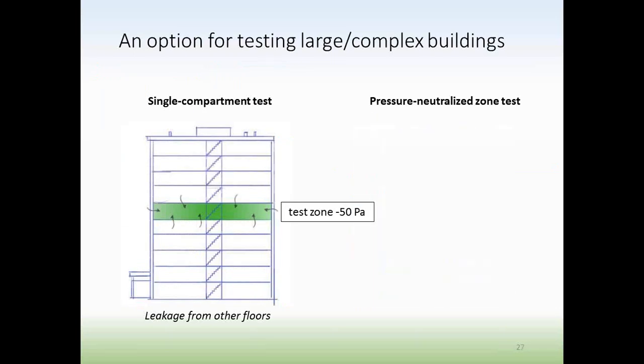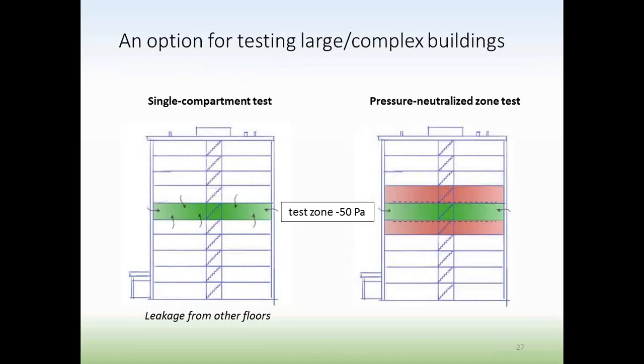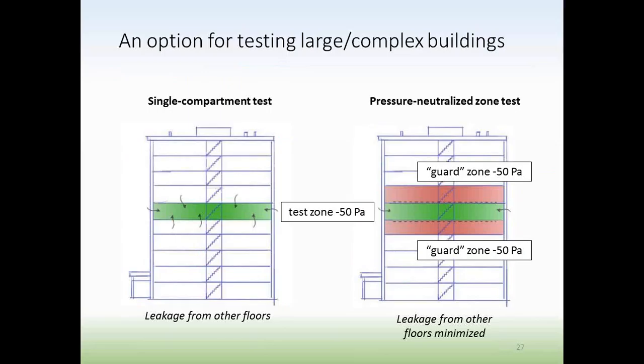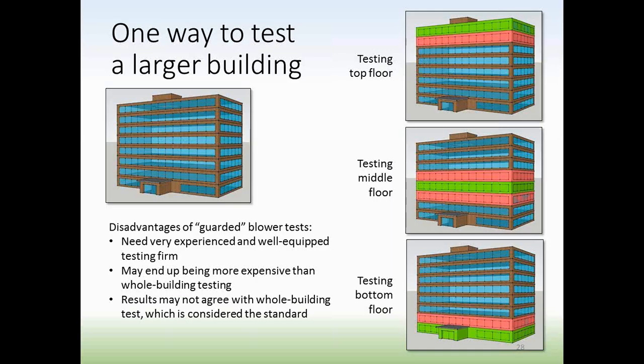A single compartment test is where you test one zone at a time, but a pressure neutralized test or guarded blower door test is where you pressurize that zone plus the ones above and below it. The pressure between those becomes equal, and so there's no leakage between them. So you cancel out leakage between zones. This is a more advanced technique. So how are you going to do this for a very big building? It might go something like this.